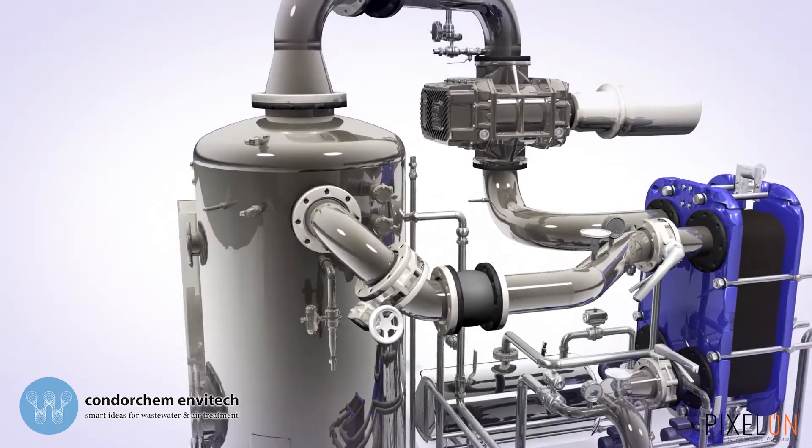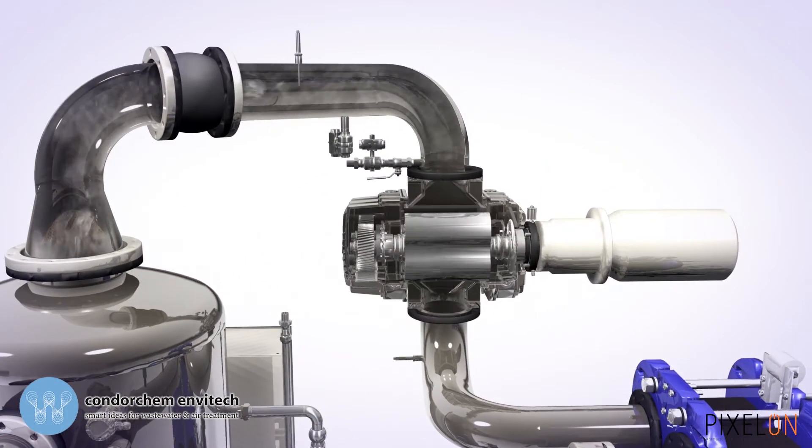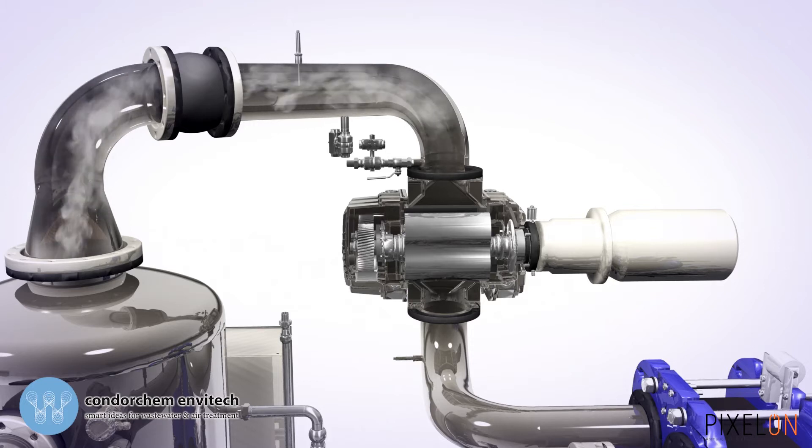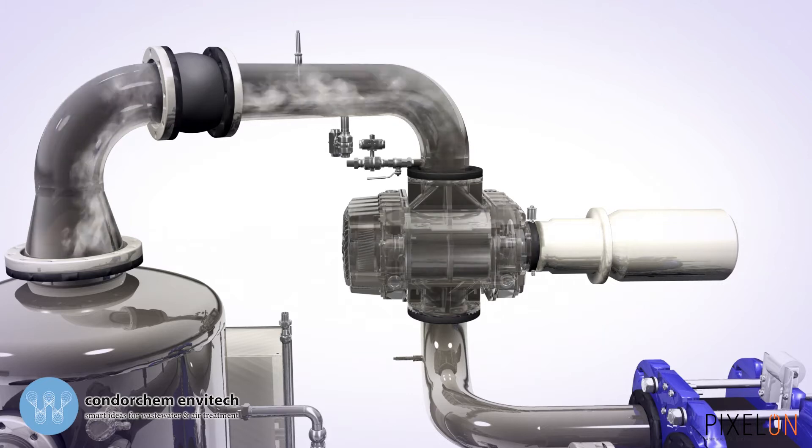From that moment, the wastewater begins to evaporate and the roots pump starts working, inhaling the vapor from the evaporation boiler. It compresses it by elevating the temperature and pressure, before sending it to the main exchanger.